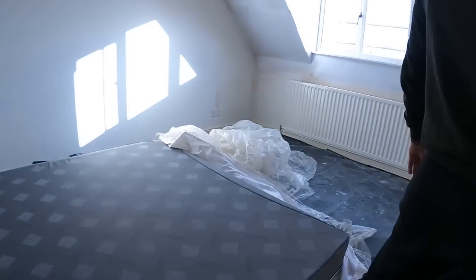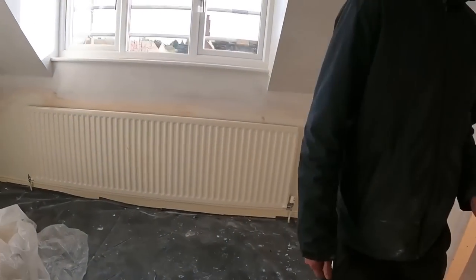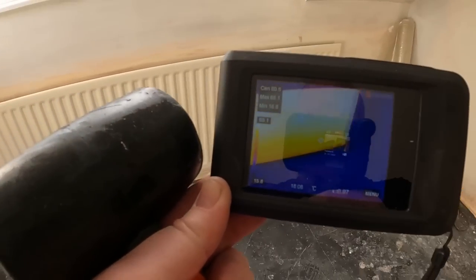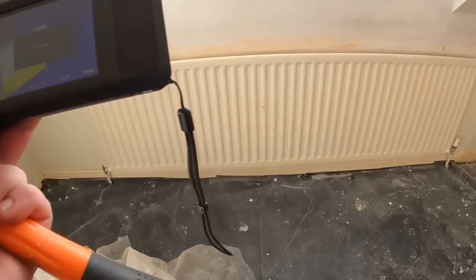And then there's also another one, slightly larger one up here. So it's this one, but no cold spots in that now. Spot on. So just come up into the roof now. While the heating system is running through with the cleaner in it, been round and checked all the rads, they're all fine, we've agitated them.